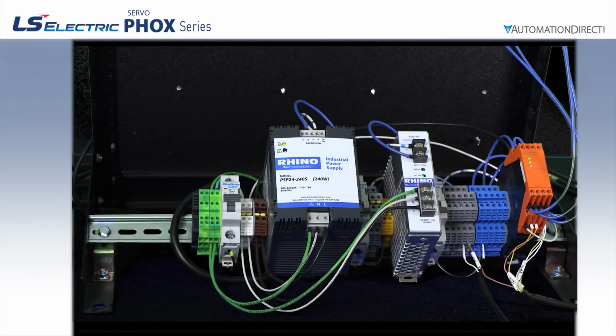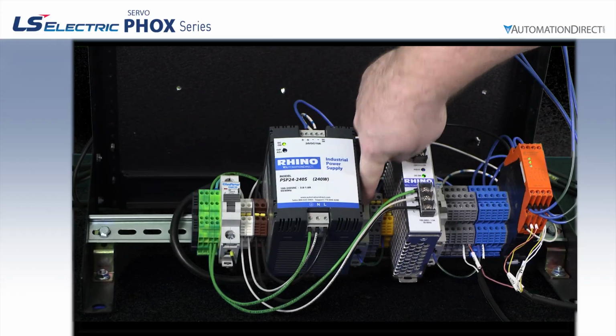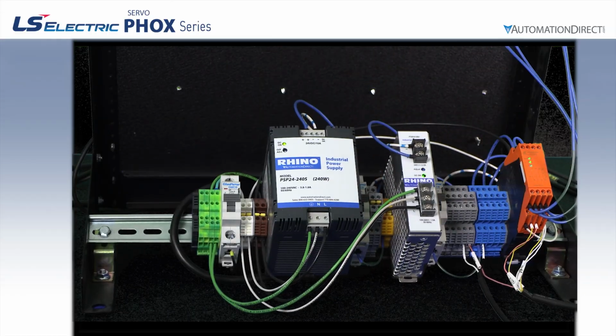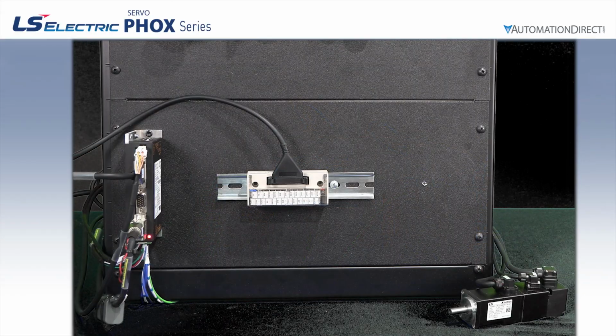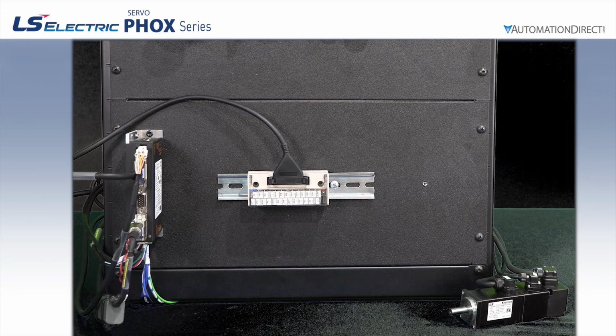And it is. Let's power up our power and control circuit breakers to send power to the drive, and we see nothing trips. If we look at the other side of our test setup, we can see the drive LED is flashing red, which indicates the drive is booted successfully and there is an error. I'll give you a little spoiler into the second video and tell you that this is perfectly normal, as the drive doesn't have a valid encoder configuration yet. But more on that in the next video.